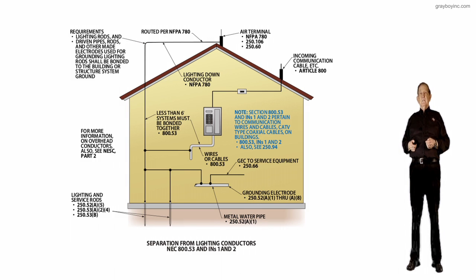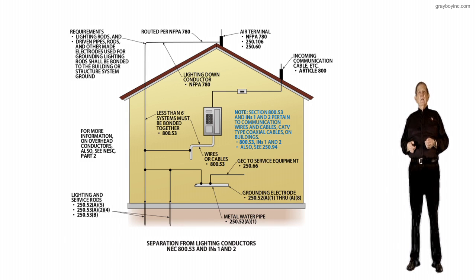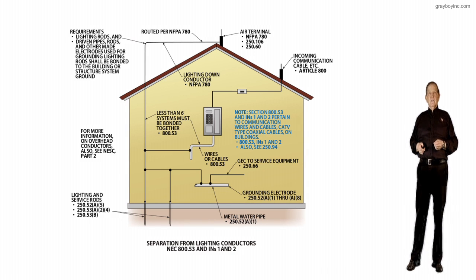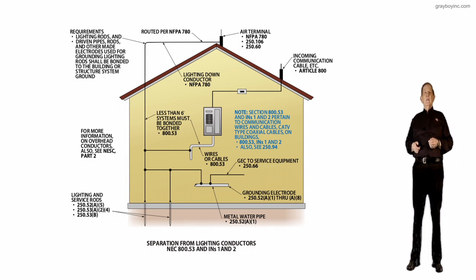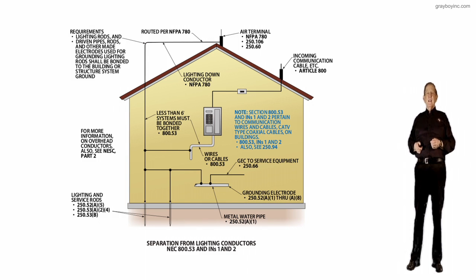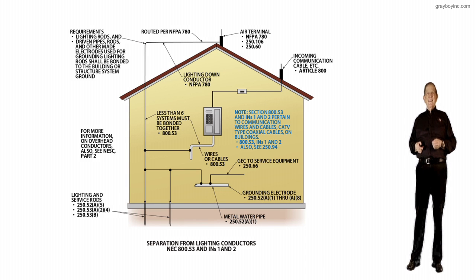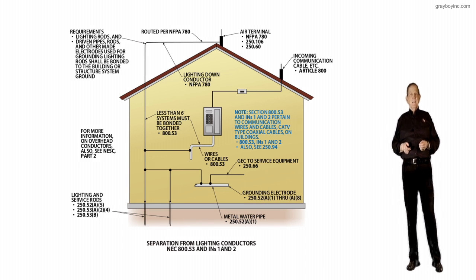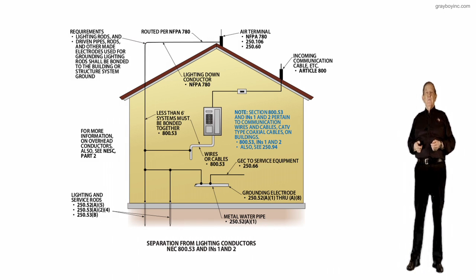Now, we notice the rods that are driven below the illustration. It talks about lightning and service rods in 250.52(A)(5), which addresses driven rods. 250.53 classifies them and basically says in (A)(2) through (A)(4) that 8 feet of those rods have to be in the earth, or put in a protective type location where you have maybe a 10-foot rod with 8 feet in the earth.